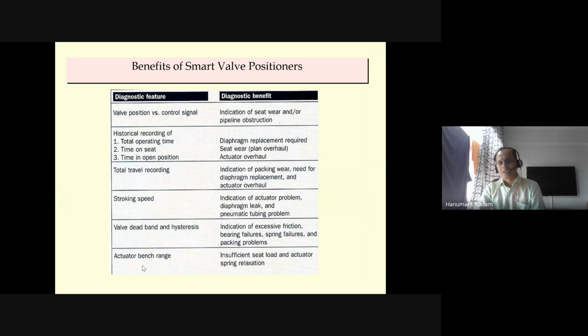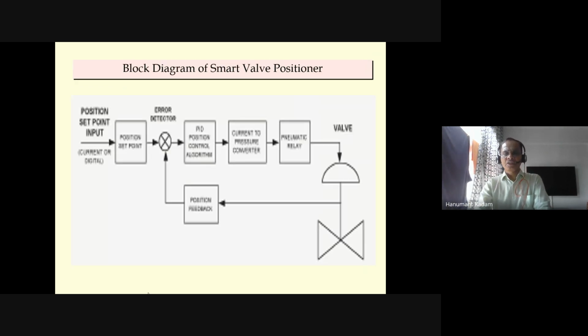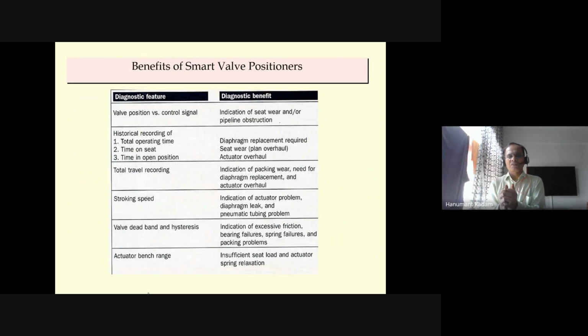If the valve is not working, valve is passing, leaking, or needs calibration, you have to remove the valve from the line. And for critical valves, sometimes you have to stop the plant. In the control valves, you can see here, control valve is a field device, transmitter is a field device. So in instrumentation or in a plant maintenance budget, on the input side, valves and transmitters, around 30% of your time is spent on transmitter maintenance. However, almost 60% of the time is spent on control valve maintenance. So more than 50% of your annual maintenance budget is for control valves.